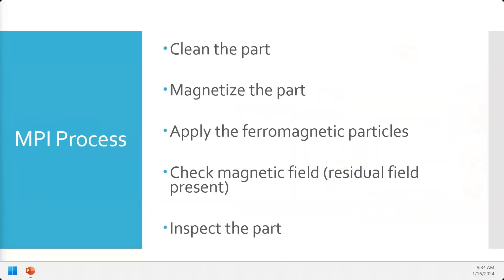When we do MPI, there's a process to follow. First, we want to make sure the part is clean. If it's covered in grease and oil, that will cause particles to stick falsely. A thick layer can prevent the magnetic field from making it to the surface. Plus, we have to run current through bare metal. If there's oil and grease on it and current heats it up, you don't want that catching fire.